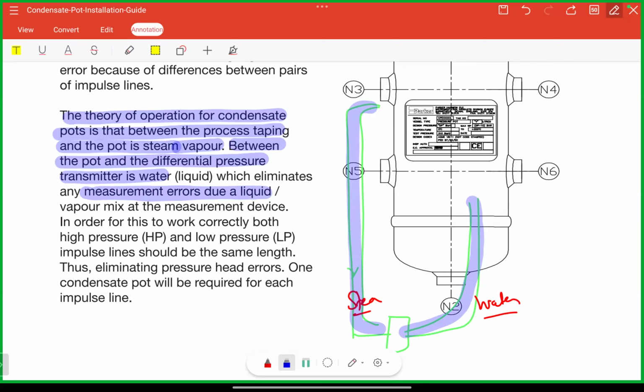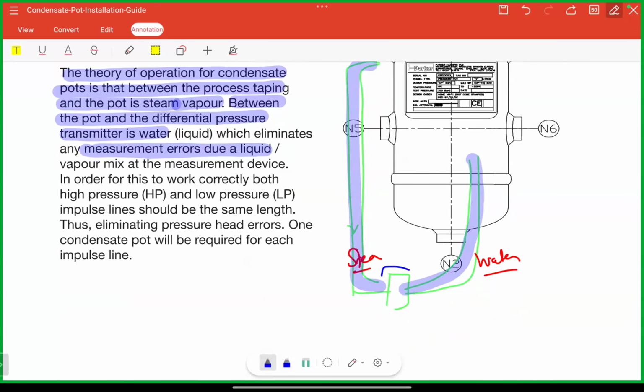Another thing, the DP transmitter itself is very sensitive. The load cell inside the DP transmitter is very sensitive. So if you are allowing steam to act directly in contact with the DP transmitter, what is going to happen? It can damage it, isn't it? Because it's continuously subjected to higher temperature. So the second reason is that it will protect the DP transmitter from the effect of high temperature fluids.